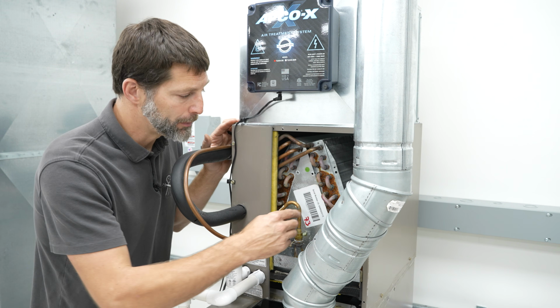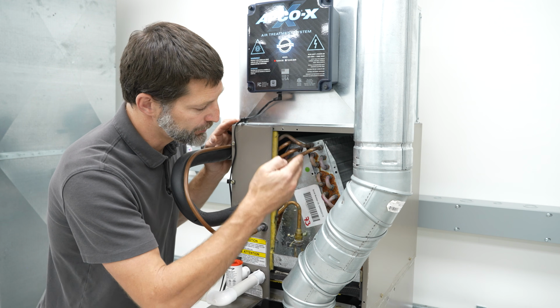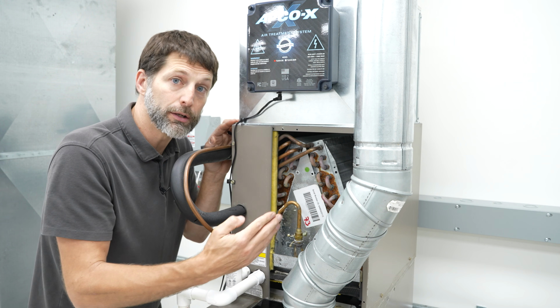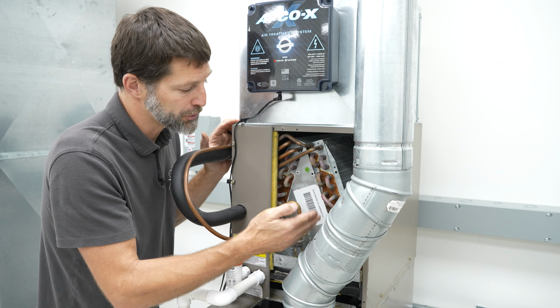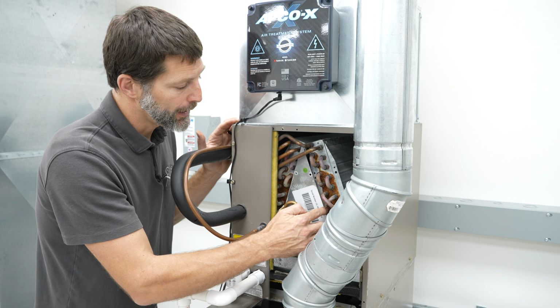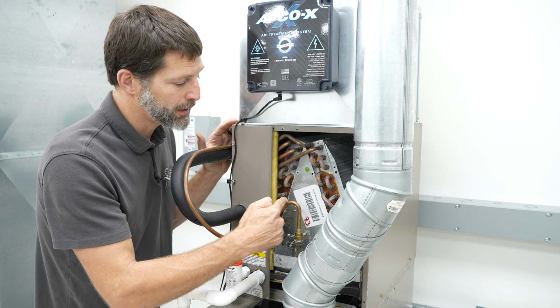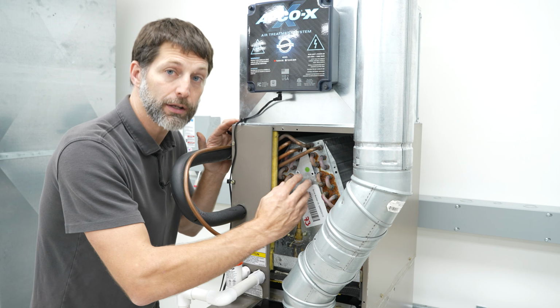The nice thing about this method is if you can completely remove this A plate right here, then you can just clean it while it's in place right here with a shop vac and the comb brush. And then you just want to make sure to reinstall this when you're done to make sure the airflow goes through the coil instead of around the coil.